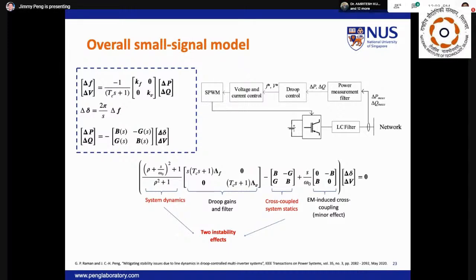The model accounts for the impact of R/X ratio, which is denoted by the variable rho. This expression represents the characteristic equation of the system, whose poles can be readily obtained by solving its polynomial eigenvalues. Furthermore, we observe that there are 2 possible destabilizing effects arising within a microgrid and highlighted in red. They are system dynamics and cross-coupled system statics. In essence, the overall small signal model of a single inverter connected to the microgrid can be modeled by a 5th order model, which is just an extension of the 3rd order Droop controller with electromagnetic dynamics of the line included.